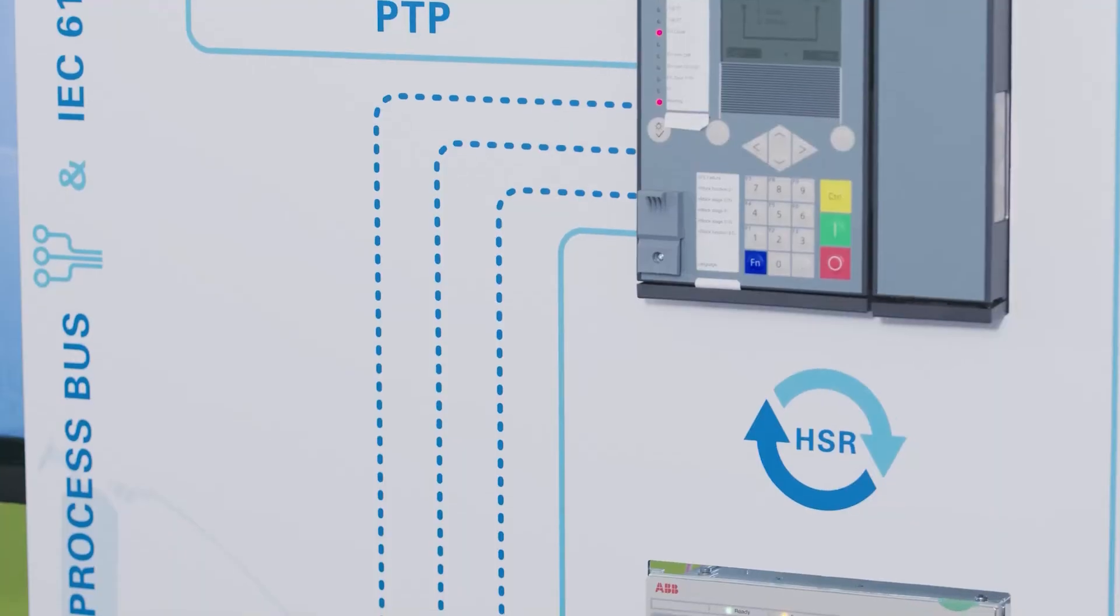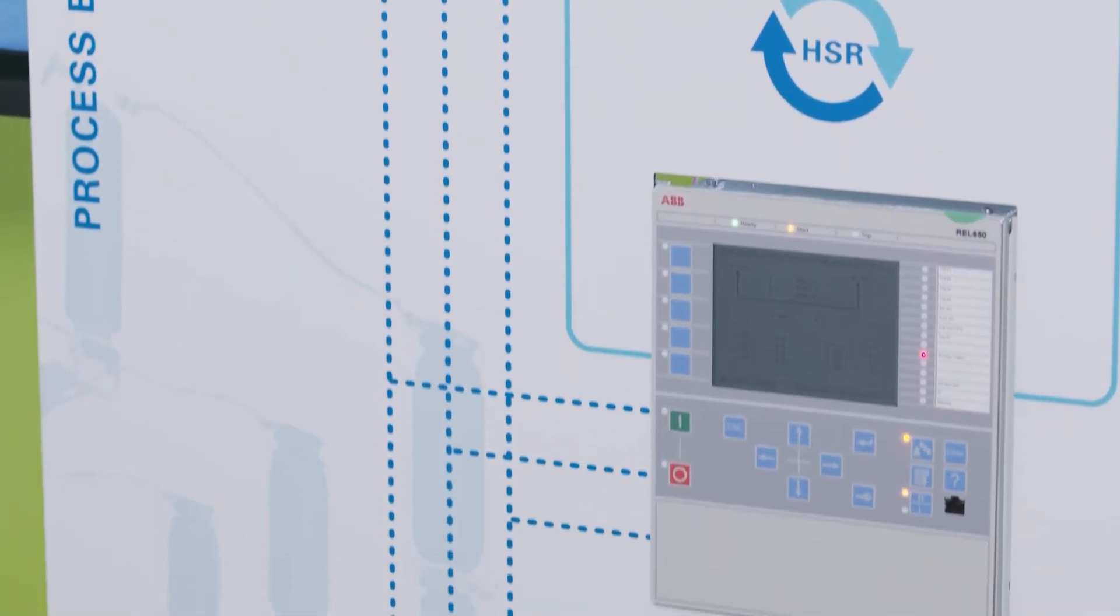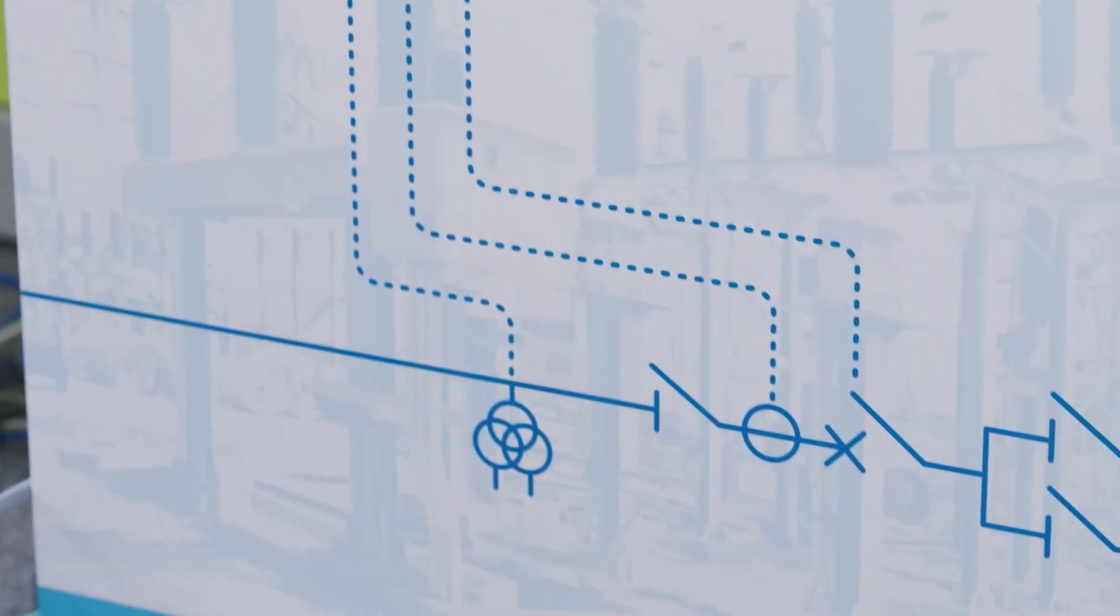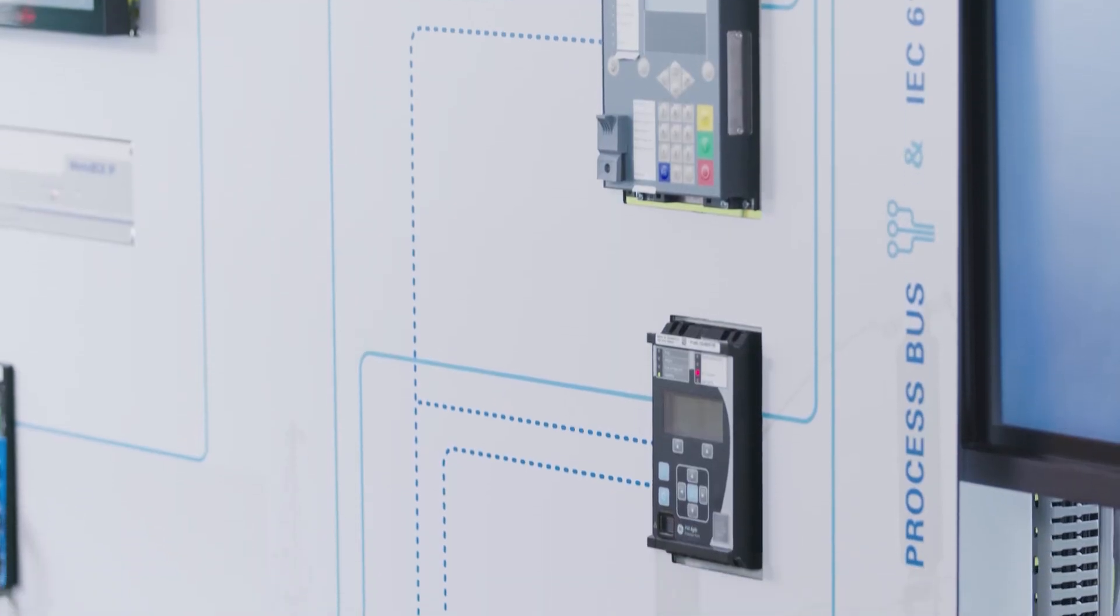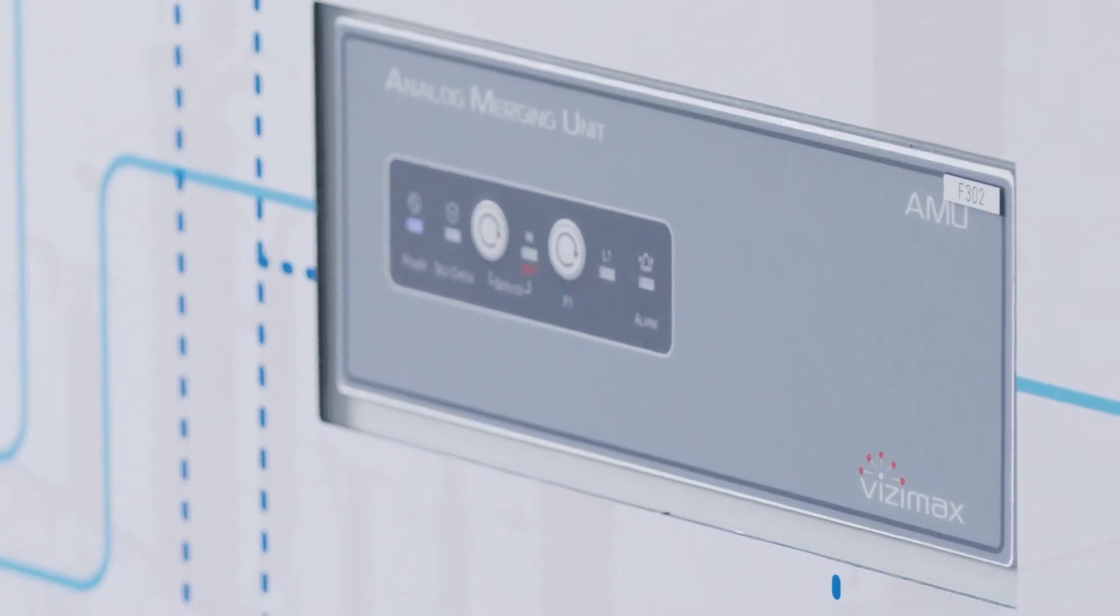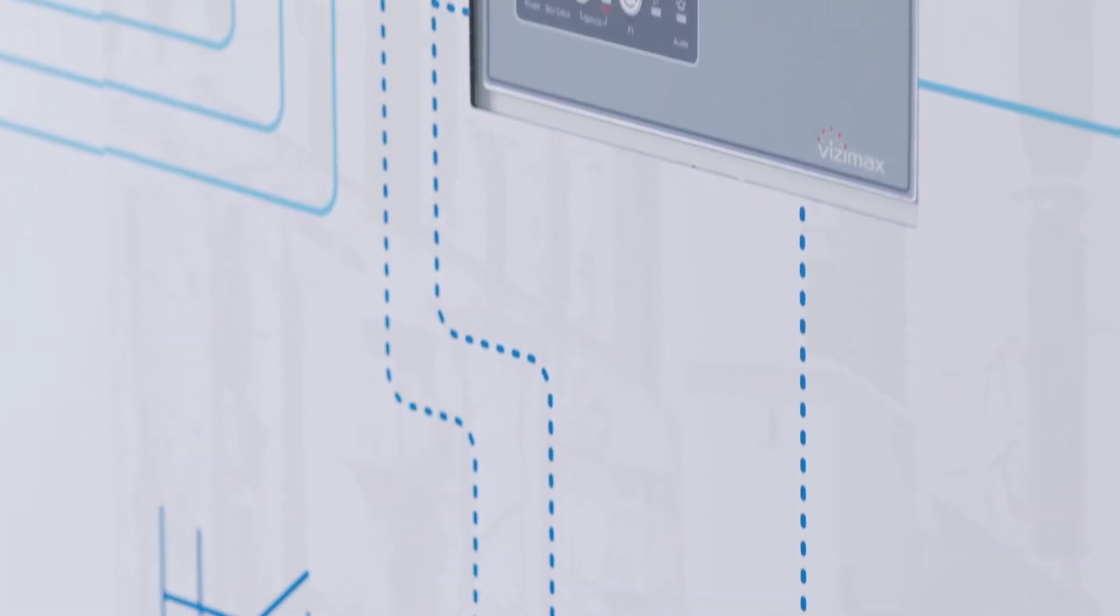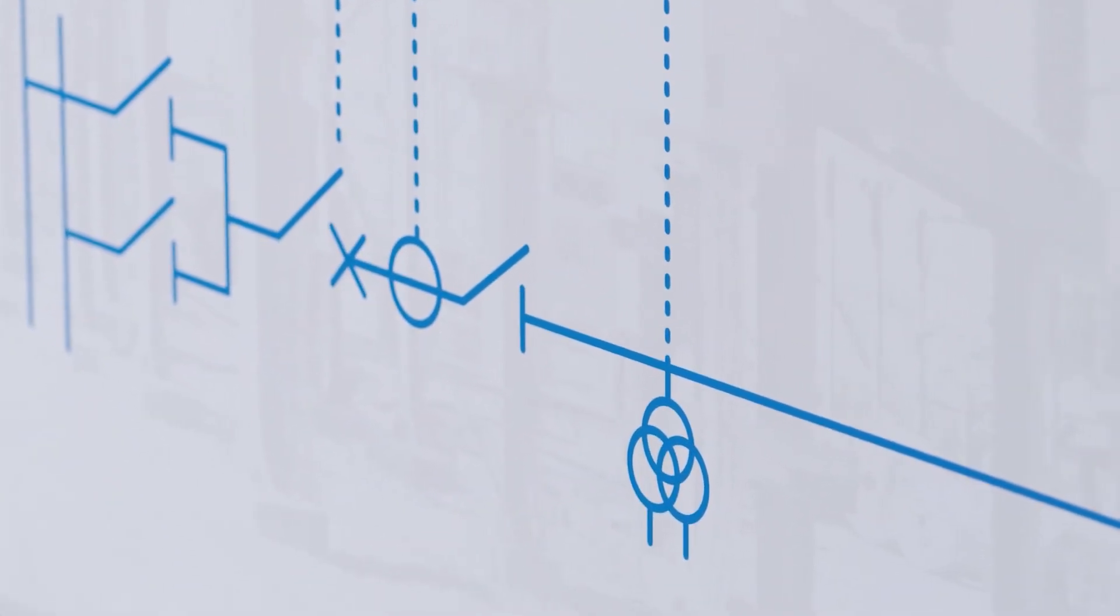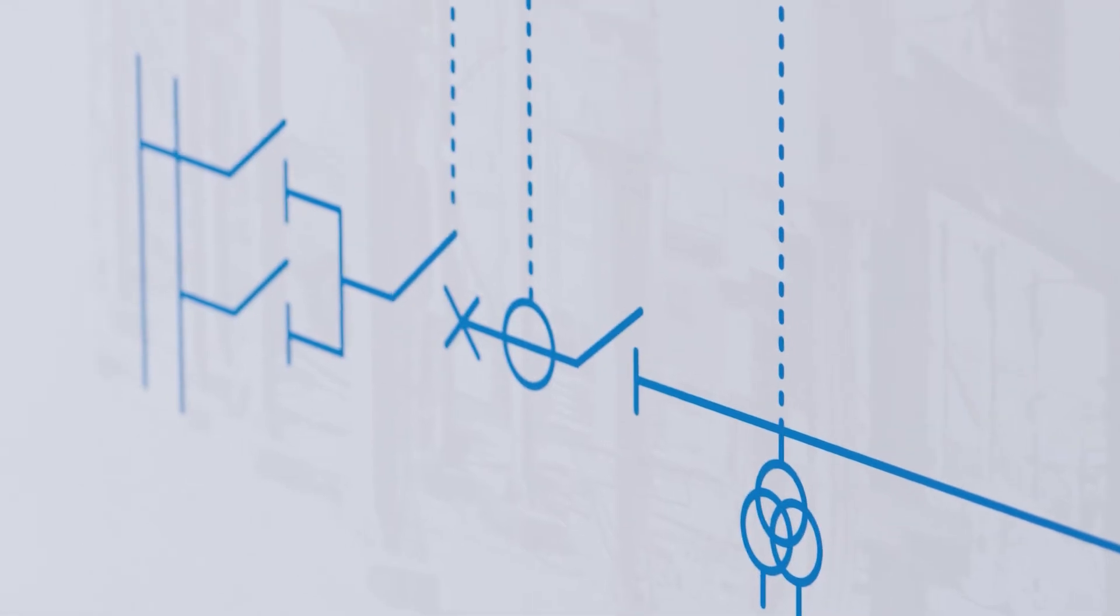In a conventional substation, the protection cabinets are connected to the measuring transformers via copper cables. Here, via the process bus, the merging unit digitizes the current and voltage information as close as possible to the high-voltage structures. The copper connections are replaced by fiber optics, thus minimizing the cost of the connections.